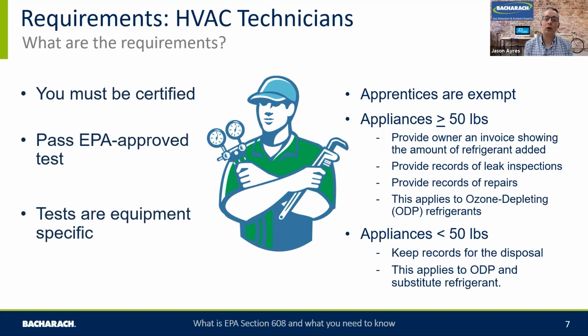So if you are doing work on equipment, especially appliances over 50 pounds, if you've added refrigerant, you need to provide information to the owner as an invoice of the amount of refrigerant added and the type as well. Also, if you've done any other repairs or inspections of that equipment, you need to supply that to the owner and operator as well. So there is some paperwork requirement at the back of this that you need to provide. And again, it applies to these ozone depleting refrigerants, so class 1 and class 2.